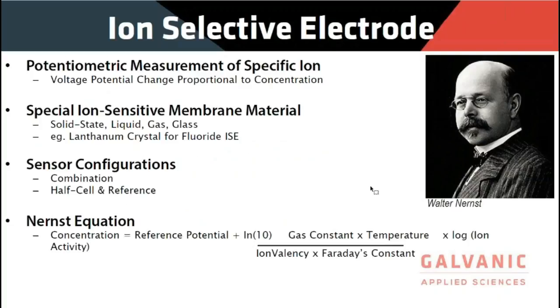ISEs, in this case, it's a potentiometric measurement of a specific ion, and so it's a voltage potential change that's proportional to the concentration of what we're measuring. We achieve this using special ion-sensitive membrane material, and so it could be a solid state, liquid, gas, or glass membrane. An example for a fluoride ISE would be using a lanthanum crystal membrane. The sensor is either configured as a combination where the half cell and reference are in the same chamber, or we can do it where they're separate. It all depends on what we think is best for the application. And again, going into some theory, this is all based on the Nernst equation.